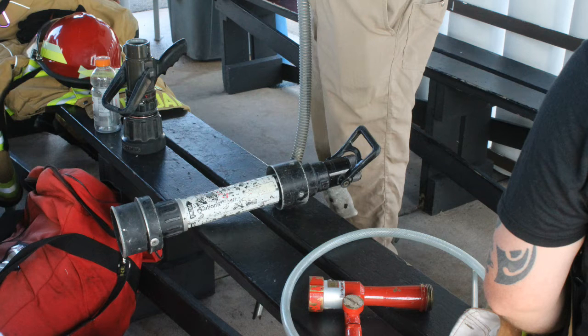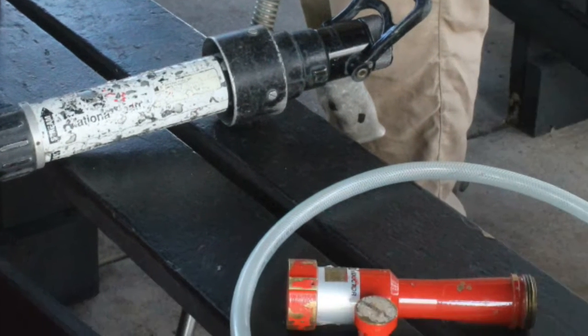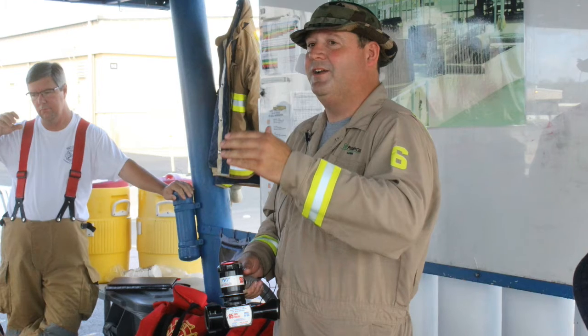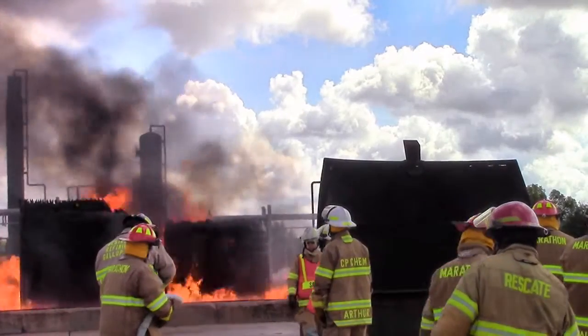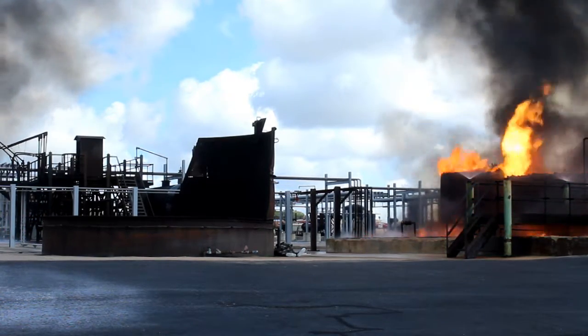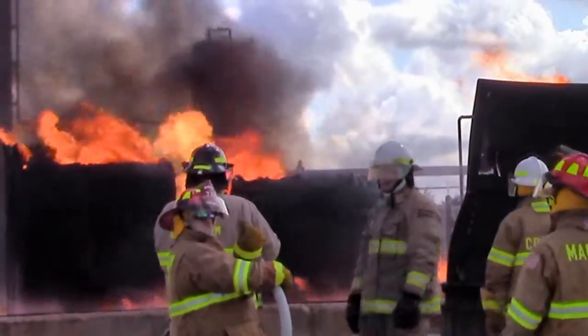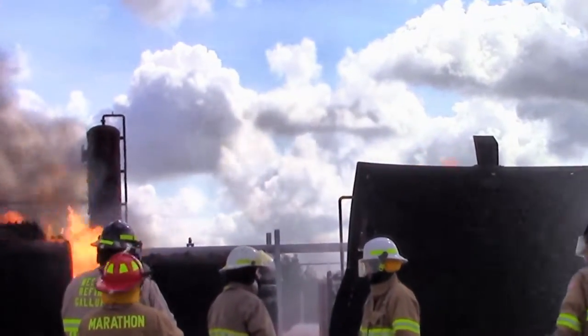To set up the eductor correctly, it has to be set to 95 GPM — or whatever matches your eductor. There are some pitfalls to look for. This eductor is 25 gallons per minute — you need to read it and confirm that. When the IC tells you to apply 95 gallons per minute at one percent training foam, it's your job to go there, pick that up, and confirm it.